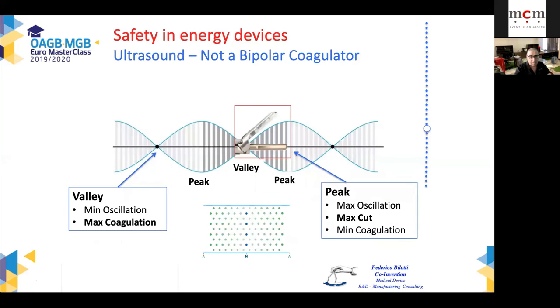If the instrument is placed next to these waves, you see that the node, which is the zero value of the wave, is at the crutch of the instrument where the two jaws meet. Then you have no vibration at that time in that site. So you have no cutting, but you have the maximum coagulation. Instead, at the tip of the instrument, where the peak of the vibration happens, the highest vibration possible, then you have the maximum cutting.